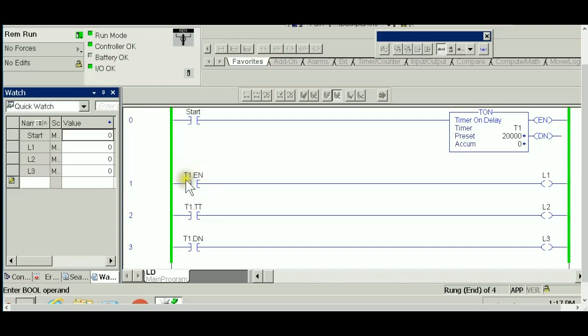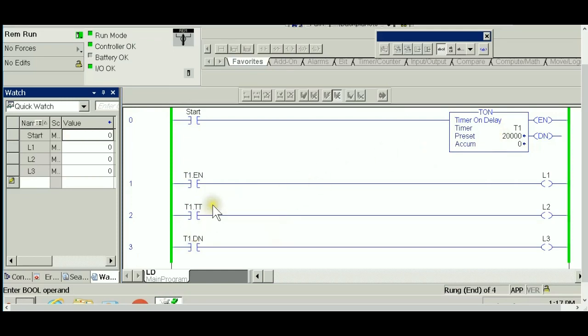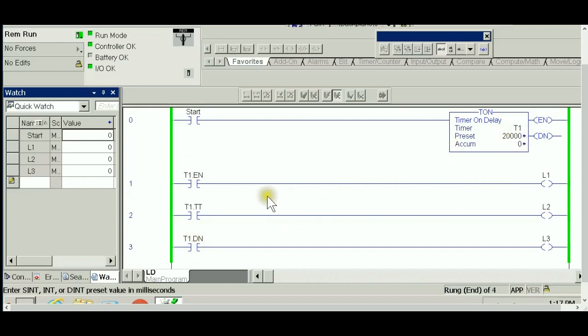Understanding that EN will follow the state of the input, and for timer timing to be true, two conditions must be met: the enable bit has to be on and the accumulator has to be less than the preset value. For the done bit to be on, the enable bit has to be on and the accumulator has to equal the preset value.